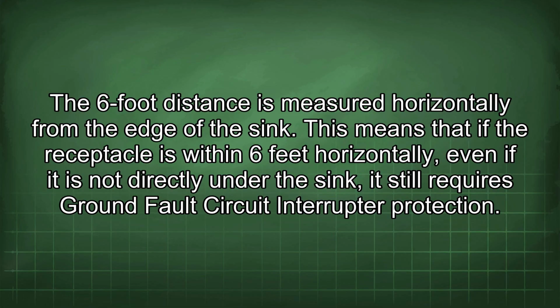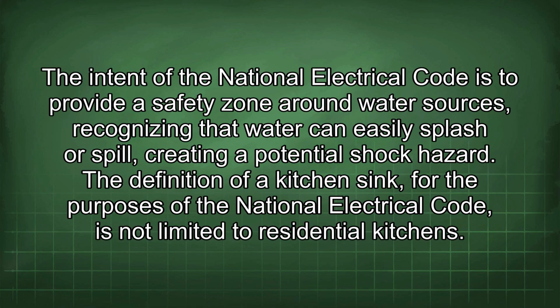This means that if the receptacle is within 6 feet horizontally, even if it is not directly under the sink, it still requires ground fault circuit interrupter protection. The intent of the National Electrical Code is to provide a safety zone around water sources, recognizing that water can easily splash or spill, creating a potential shock hazard.